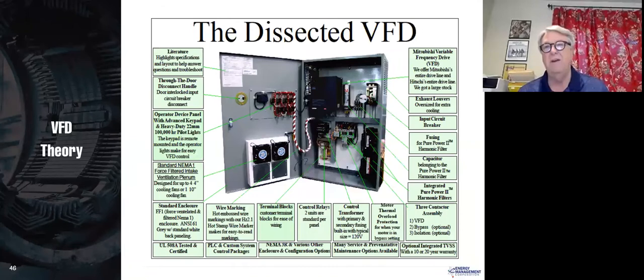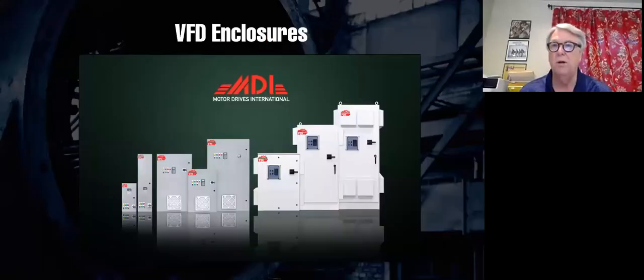Here's a dissected VFD, shows all the parts inside. I'm not going to go into that in detail due to time. Here we have our three enclosures. The enclosures on the left are non-ventilated, in terms of they're not forced ventilated, and they don't have filters on there. They're the cheapest ones, and they do have a steel enclosure, and so they're nice for arc flash and so on. But I recommend these ones over here in the middle because they're forced fan and filtered, and if you keep those filters clean, those drives are going to last a long, long time, and the inside of that enclosure is going to be very clean.